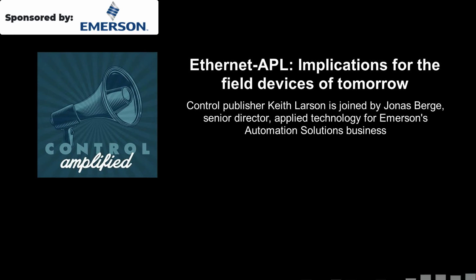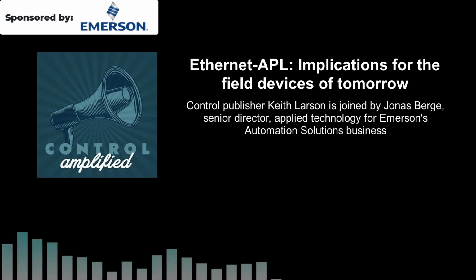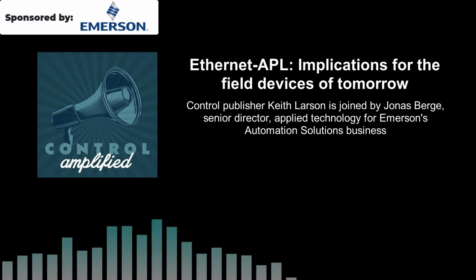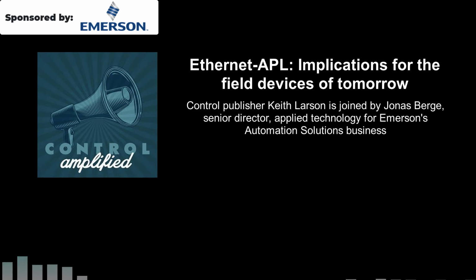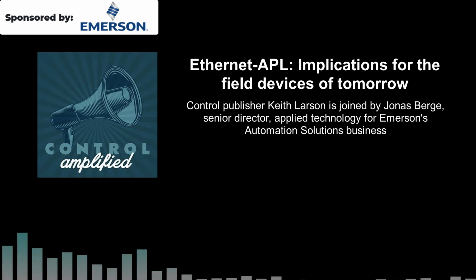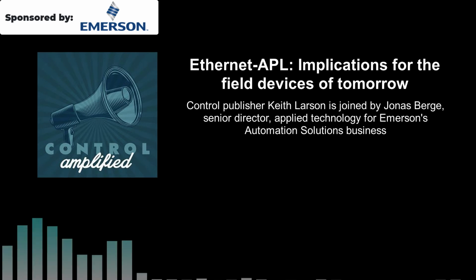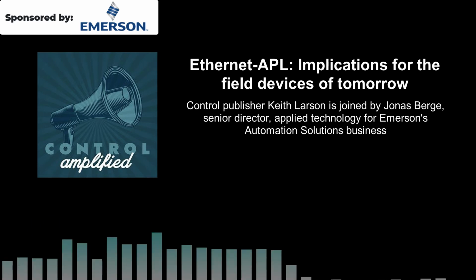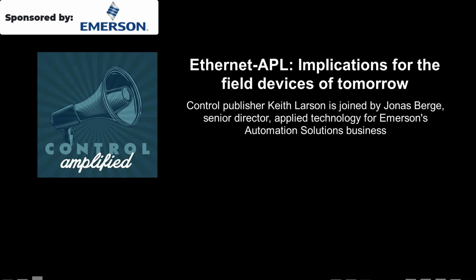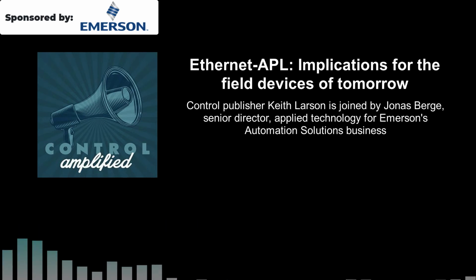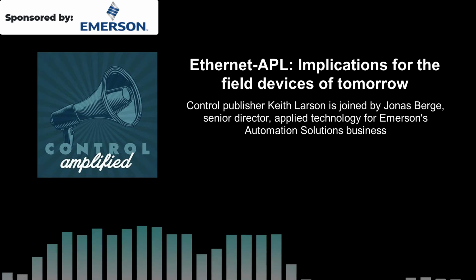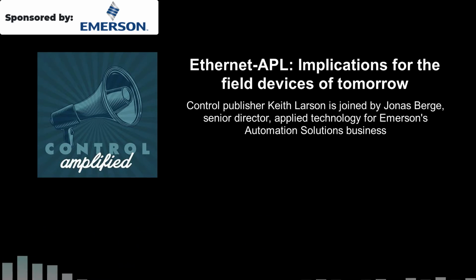That sounds like it would cut startup time off a project for sure. Another good example is gas analyzers. Imagine installing gas analyzers in the field near the process sampling point, with minimal sampling lines, and using APL to run the data back to the people who need it. This is a lot easier to build and maintain than constructing analyzer shelters and laying and maintaining long sampling lines the traditional way.